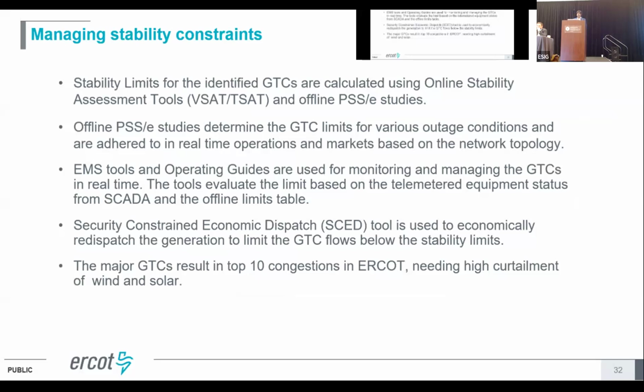So we have real-time VSAT and TSAT calculating the limit, and then we have another tool called the Transmission Constraint Manager, which gives the operators situational awareness on what all the interfaces are currently doing, what their expected limit is, and how far we are from hitting that limit. They calculate the available stability margin for each of these interfaces, and then they try to maintain enough margin to not let the flow in the base case ever exceed that stability limit. So we always try to keep it.